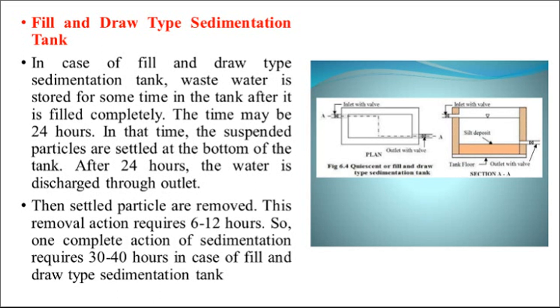One complete cycle of sedimentation requires 30 to 40 hours in the case of fill and draw type of tank. Hence, when using a fill and draw type of sedimentation tank, one standby unit must be constructed. This figure shows the plan and section of the fill and draw type of sedimentation tank.